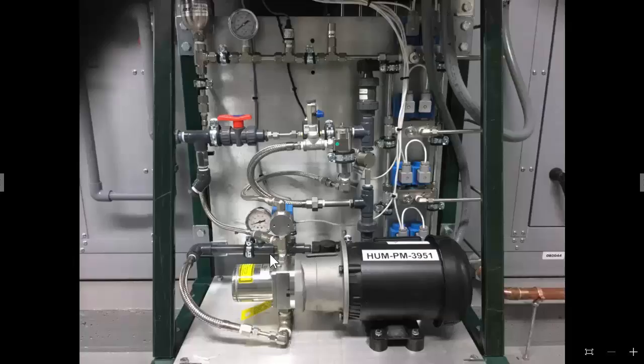Danfoss would like to see the use of JIC fittings as much as possible, but the JIC fittings are a little more expensive, a little more hard to come by as far as the right fittings are concerned. And in the United States, here in North America, we have a tendency to lean towards NPT, National Pipe Thread fittings. These valves here, these with the 2 solenoids on them, they are Danfoss also. They are NPT fittings. However, Danfoss does make a valve assembly like this with British standard parallel pipe threads, BSPP fittings.